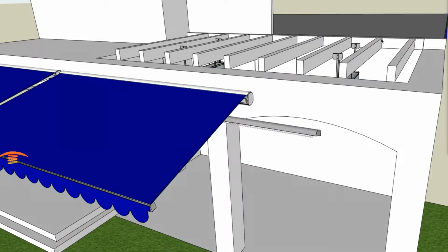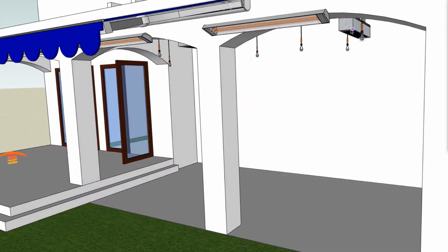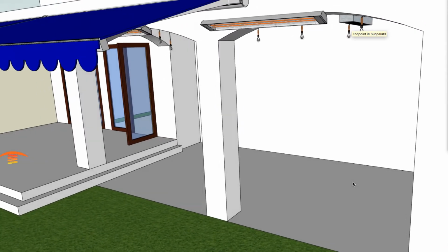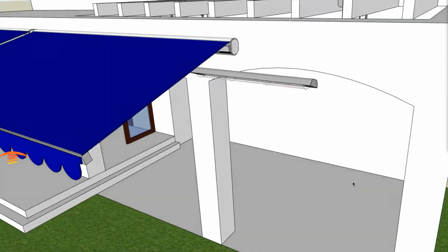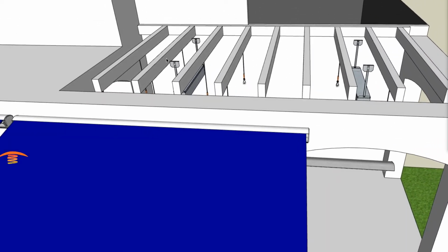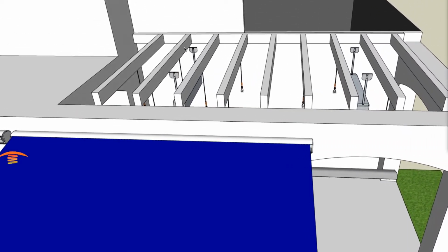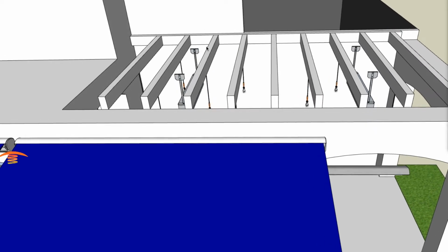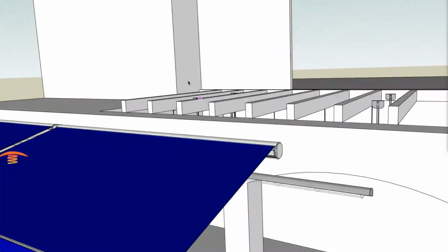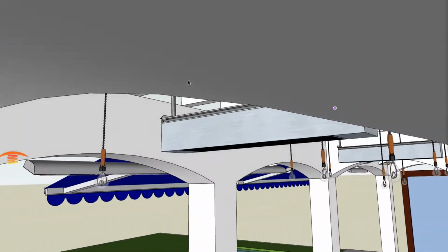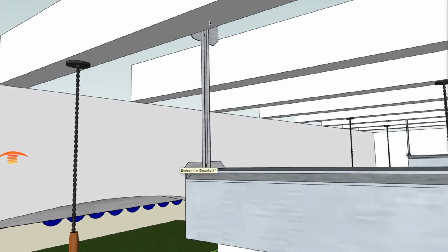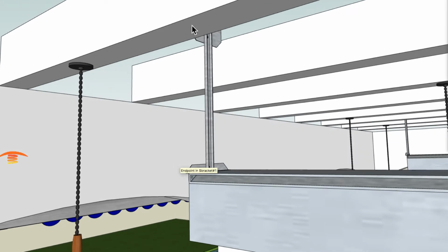The other thing is where I believe we're at 9 foot, 4 inches off the finished floor here, which is another perfect part of the application. And up here you could take a piece of Unistrut or wooden beam and just place it across the top to support these heaters themselves. And for my clearances, I'm meeting clearances from this top edge of the patio to the actual beams going across here.